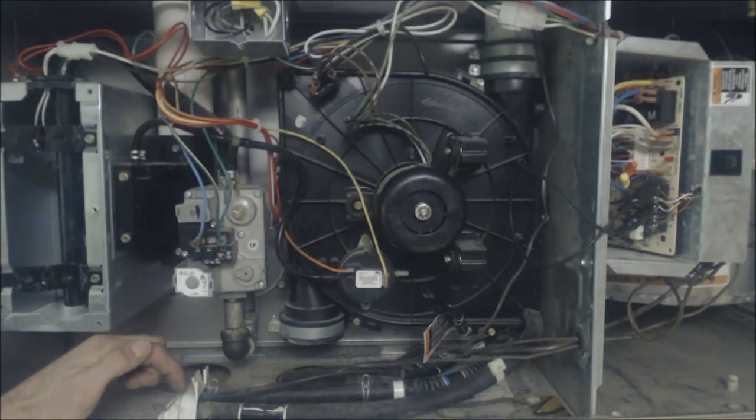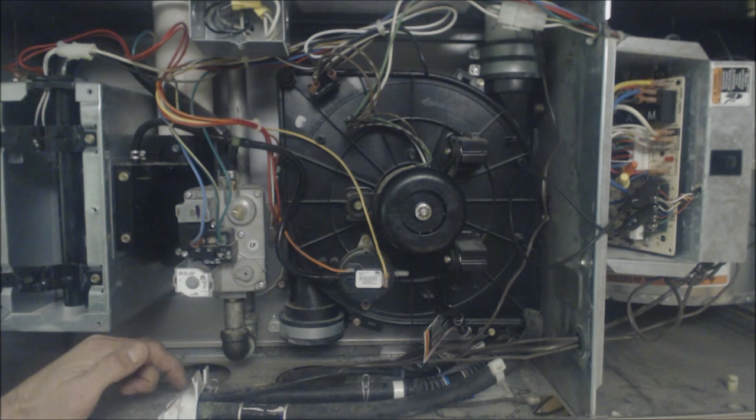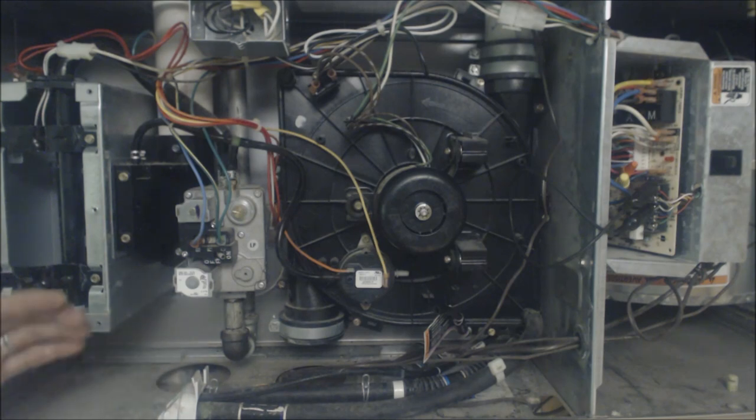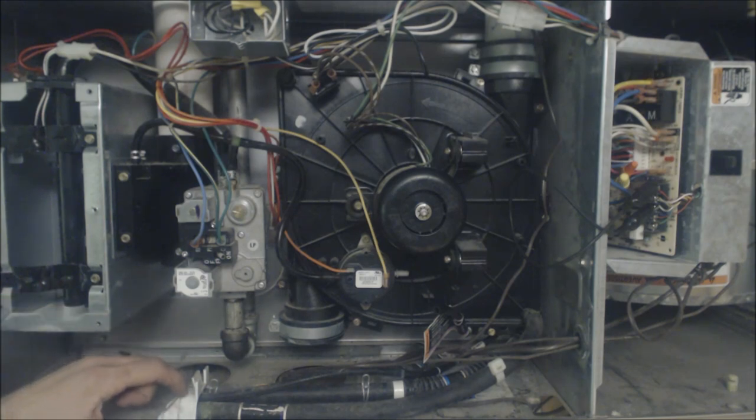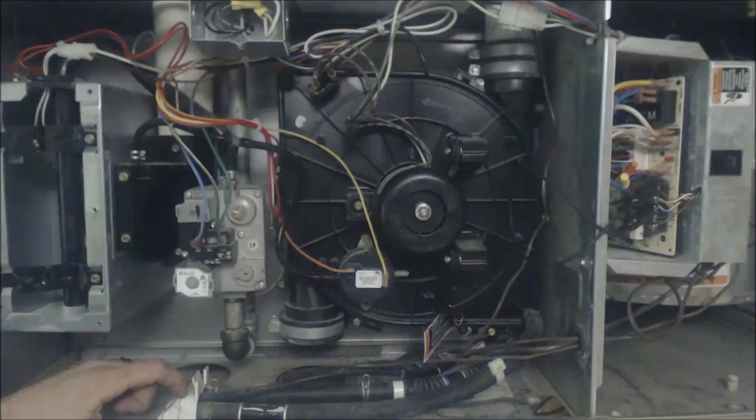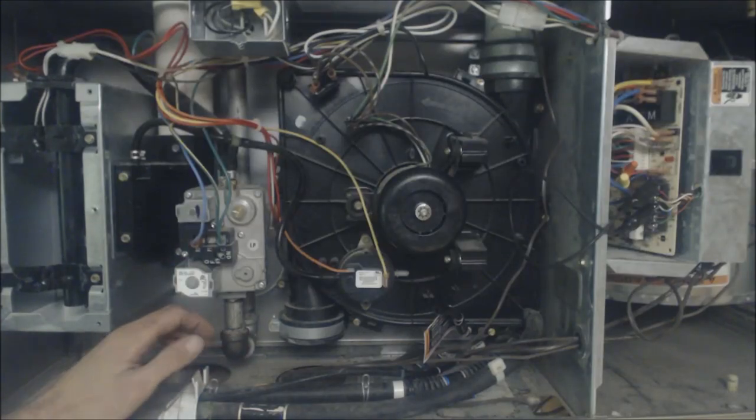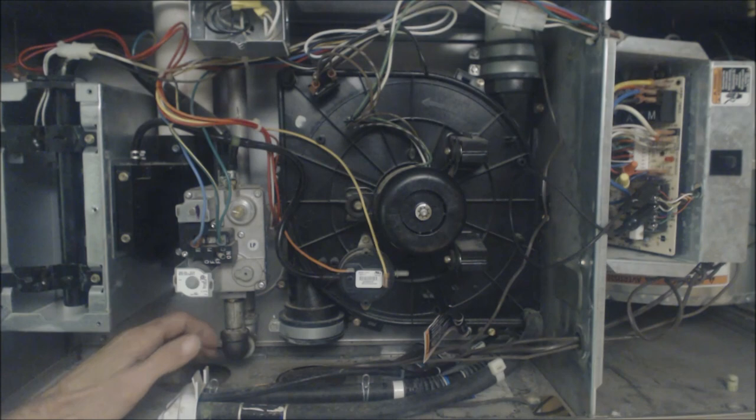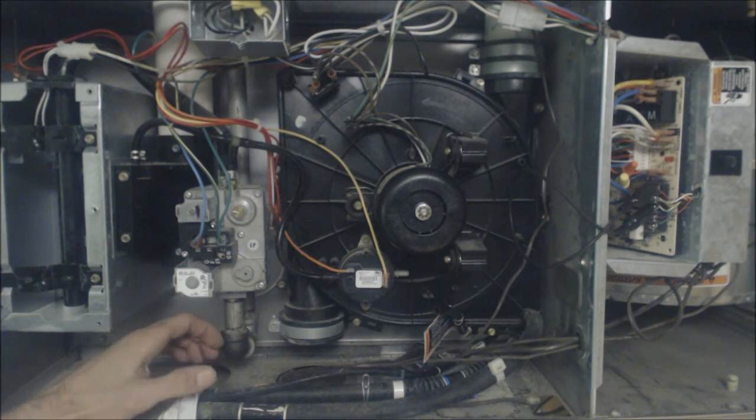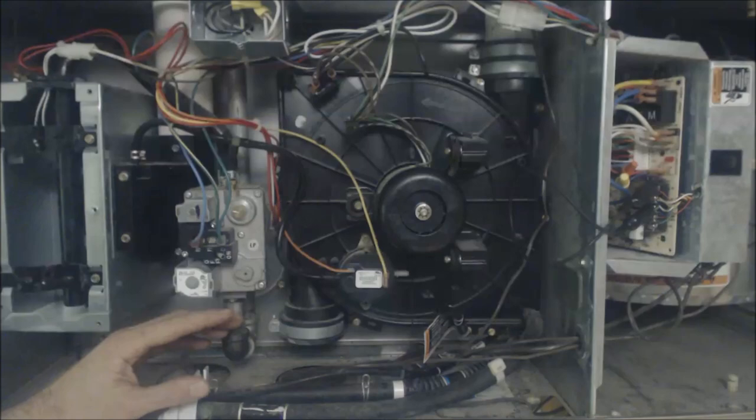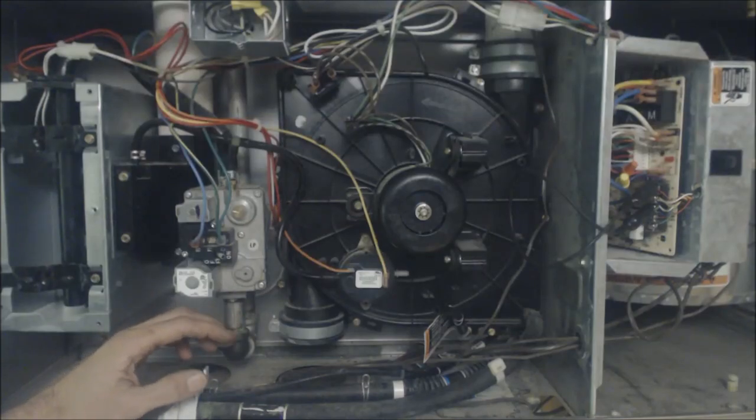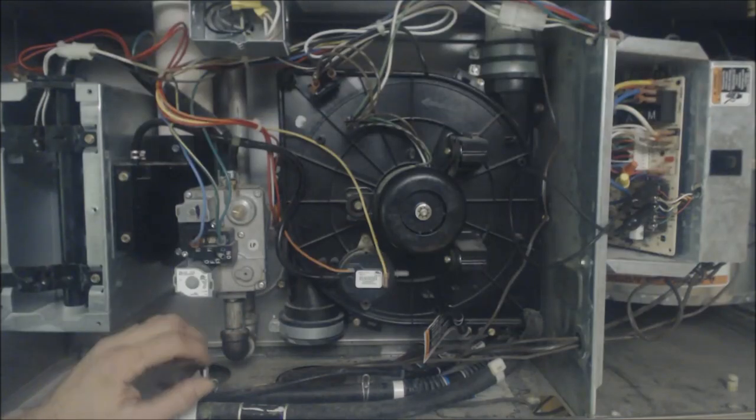But I've seen it where somebody doesn't run the condensate pipe correctly, it goes back uphill a little bit, it clogs up, you know, water sits between seasons, you know, maybe it's sitting there all summer and it just gets all gunky and sludgy and that's where the clog is.